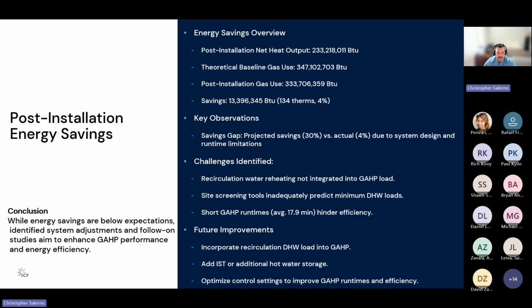So the next step that we're planning on doing is incorporating the recirculation load into this. Another challenge identified here was the site screening tools. Initially there was not really any. We used the ASHRAE site screening tool, but it inaccurately predicted the minimum heating load, and so that led to the shorter run times, and the small heat exchangers also didn't maximize the performance of the GHP when it was running. So a few things there led to the shorter run times from the design.